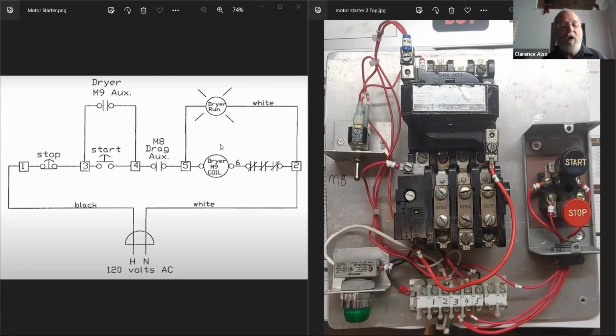You gotta fix it where you got the problem. So I'm saying you got 0 volts there. Okay, so if you had 0 volts there and you're expecting 120, which direction do we go? We want to start leaning more towards the start button. Okay, good point. Here's a start button with the 3 side or the 4 side. We can put one at 3 and one at 4 to see if we've got power going through the start button - pressed on the terminals, could easily do that.